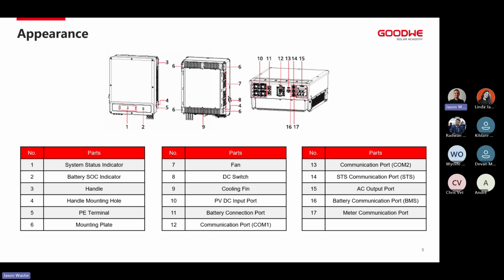If we connect it to an STS, we'll connect from port 15, the AC output port, into the STS, and the STS will then be able to distribute the power either into our backup loads or back into the grid if we are allowed to export.